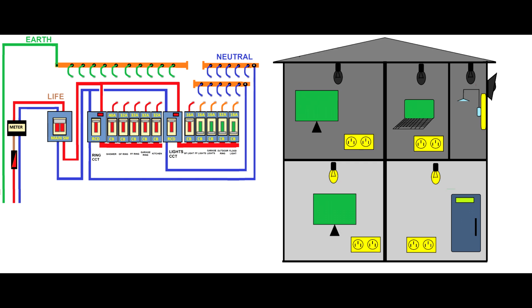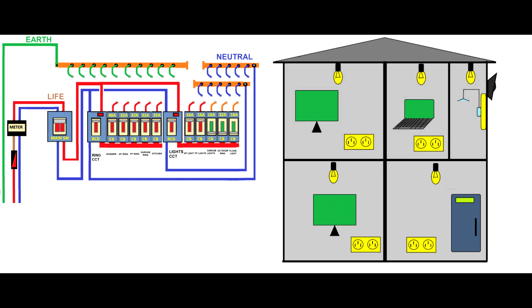I'm waiting for a while to see if that circuit will trigger the residual current device. By doing this very fast and being satisfied with the fact that you didn't have an instant trip of the residual current device, it is not a good idea, because that circuit might have a delay in triggering the fault.